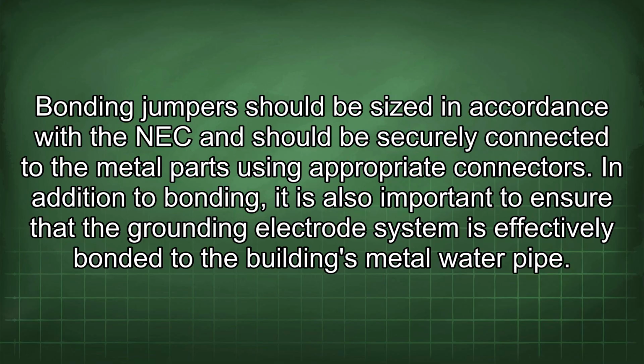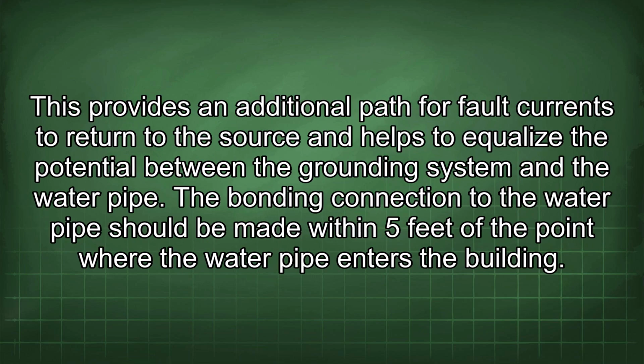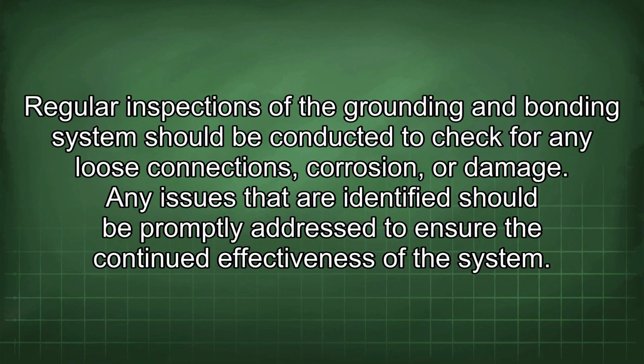Bonding jumpers should be sized in accordance with the NEC and should be securely connected to the metal parts using appropriate connectors. In addition to bonding, it is also important to ensure that the grounding electrode system is effectively bonded to the building's metal water pipe. This provides an additional path for fault currents to return to the source and helps to equalize the potential between the grounding system and the water pipe. The bonding connection to the water pipe should be made within 5 feet of the point where the water pipe enters the building. Regular inspections of the grounding and bonding system should be conducted to check for any loose connections, corrosion, or damage. Any issues that are identified should be promptly addressed to ensure the continued effectiveness of the system.